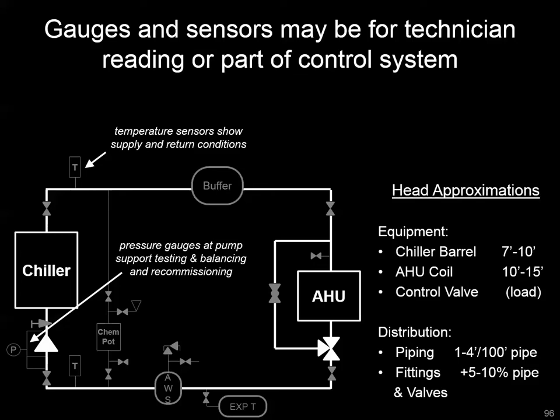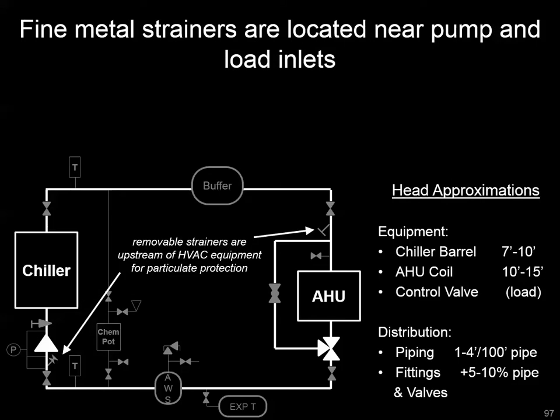You also have control devices and gauges — such as a pressure gauge across the pump and the pump strainer — and temperature sensors throughout the system that may be standalone or connected to your automation system. There are also removable strainers that should be upstream of any important piece of equipment like a pump or a coil. Those can be cleaned, and hopefully you have a gauge nearby to check if you have a clogged strainer that needs to be removed, replaced, or sprayed out.